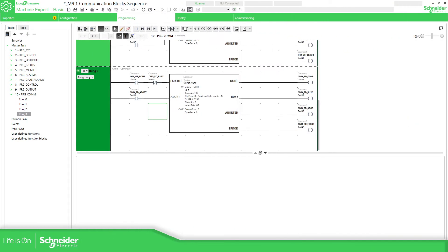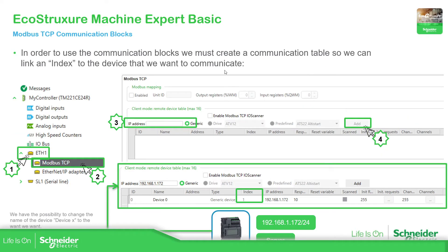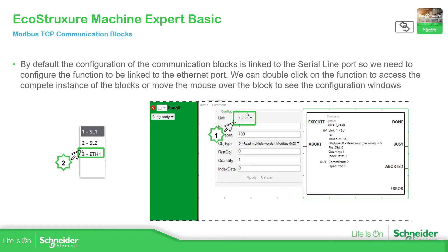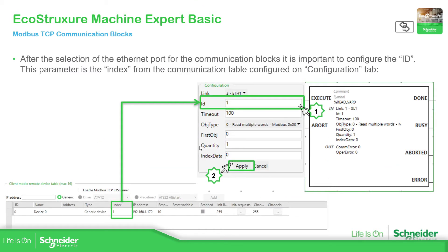In the programming tab, find the arrows to add function blocks and select the one you want to use: read, write, or read-write. Once defined, select the link or port you want to communicate through. By default it shows serial line one, but in our case we use Ethernet port one. The other thing to link is the ID, which connects to the index of the devices already defined in the table — in our case, index one, and so on if we add more devices.